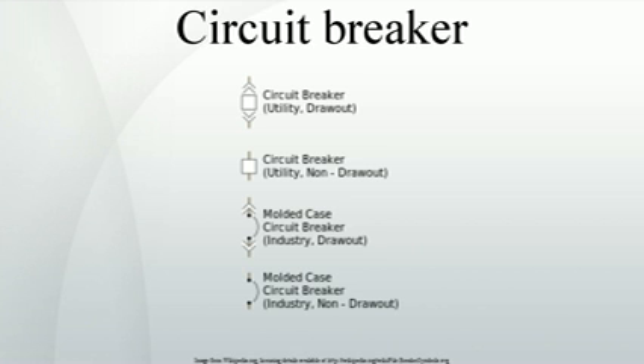Thermal magnetic circuit breakers. Thermal magnetic circuit breakers, which are the type found in most distribution boards, incorporate both techniques, with the electromagnet responding instantaneously to large surges in current, short circuits, and the bimetallic strip responding to less extreme but longer-term overcurrent conditions. The thermal portion of the circuit breaker provides an inverse time response feature, which trips the circuit breaker sooner for larger overcurrents.